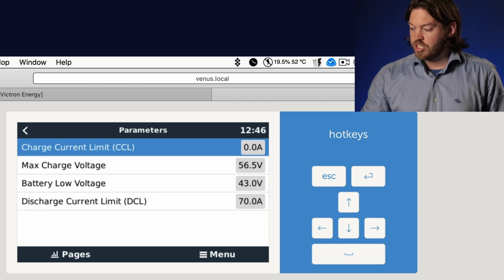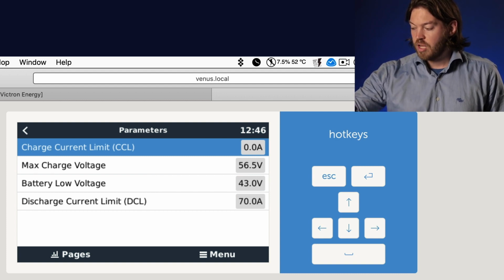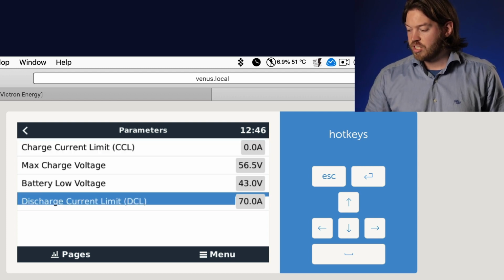So they're showing a charge current limit of 0. We hope this is going to increase shortly to 70. We can see the discharge current limit is 70 — that's 2 batteries, each giving 35 amps. If you had 3 batteries, you'd see 105 amps, hopefully.